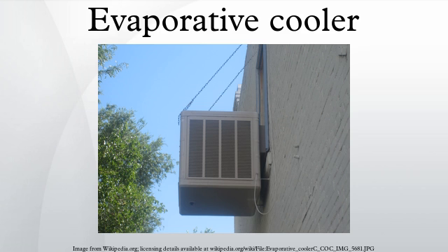Performance. Understanding evaporative cooling performance requires an understanding of psychrometrics. Evaporative cooling performance is variable due to changes in external temperature and humidity level. A residential cooler should be able to cool air to within 3–4 degrees Celsius of the corresponding wet bulb temperature. It is simple to predict cooler performance from standard weather report information. Because weather reports usually contain the dew point and relative humidity, but not the wet bulb temperature, a psychrometric chart or a simple computer program must be used to compute the wet bulb temperature.